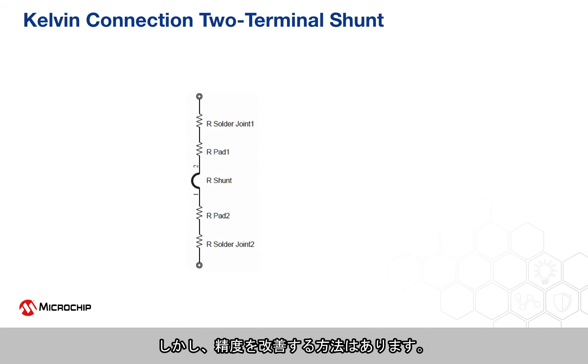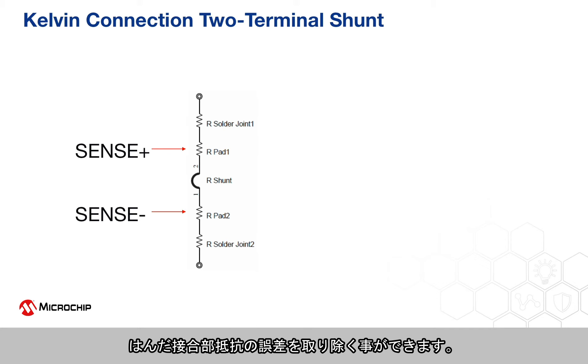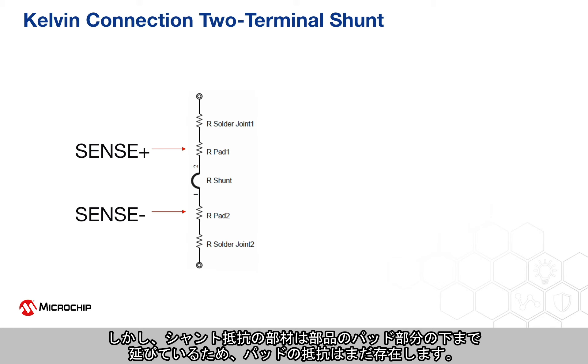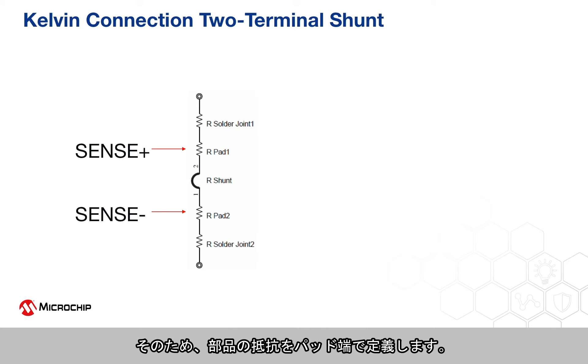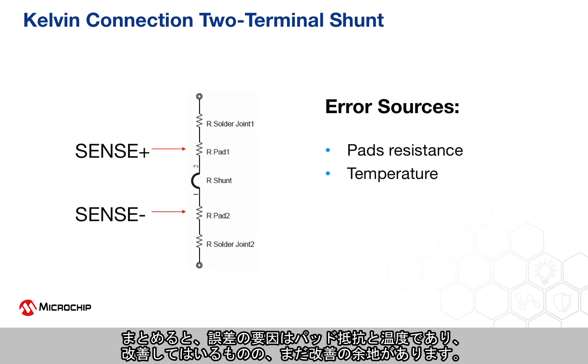There is, however, a way to improve the accuracy. This is called Kelvin connection, and it taps into the inner bottom edge of a shunt terminal. The solder joint resistance error is eliminated. However, the pad resistance is still present because the shunt material extends under the pad area of the component — the actual resistance of the physical component is defined at the extremities of the pads. It is also highly susceptible to assembly position errors, as the component will float unevenly on the solder pads. In summary, the error sources are pad resistance and temperature — a big improvement from before, but there is room for more.